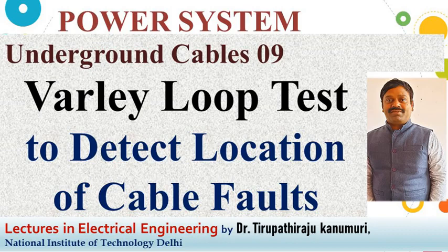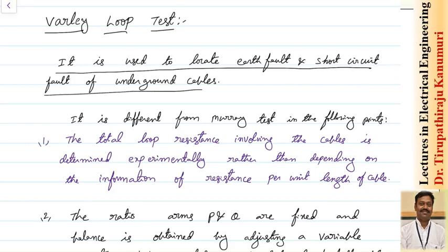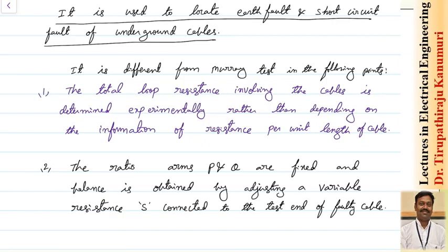Hi all, today we are going to discuss the Varley loop test for detecting the location of faults in cables. It is used for locating earth faults and short circuit faults of underground cables. In the last class we saw the Murray loop test. It differs from the Murray loop test in the following respects.